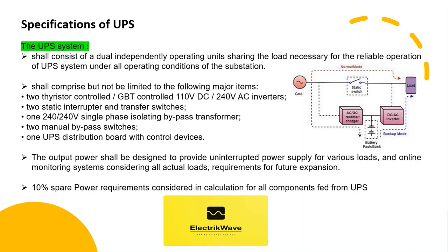The UPS system shall consist of dual independently operating units sharing the load necessary for reliable operation under all operating conditions of the substation. UPS shall comprise, but not be limited to: two thyristor-controlled or IGBT-controlled 110V DC to 240V AC inverters, and two static interrupter and transfer switches.